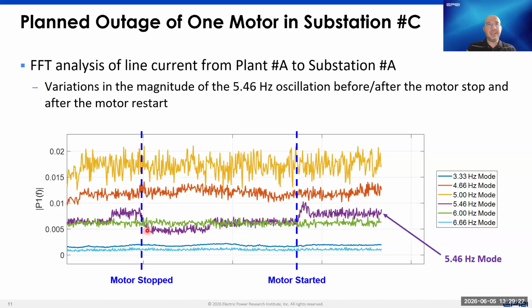So this is another kind of validation that the motor was creating, or is one of the sources of those oscillations. You see here that the energy got reduced, but then here you see a small increase, and what we suspect here is that the value is below the pre-event value.